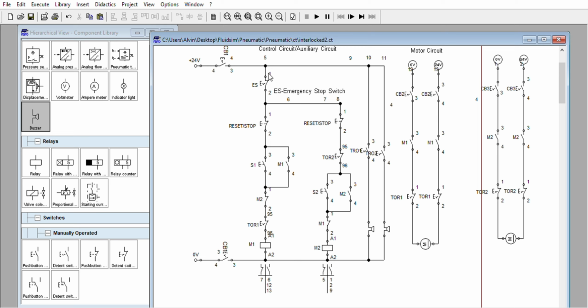Even though this is turned off, you cannot see that way, but in some cases they will do that one. Usually, if this is key operated, you can have key operated emergency stop push button. You can have another series mushroom type emergency stop push button for security. The key operated is for more security, more safety.